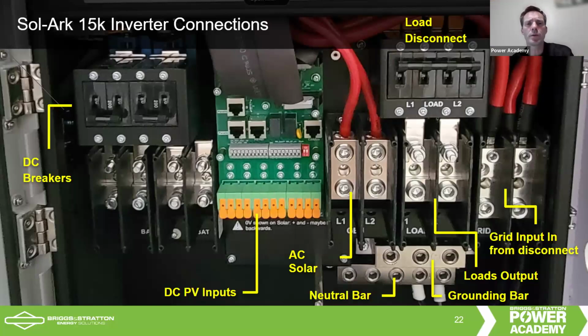So open circuit voltage on your panels should be a max of 550. Do take into consideration if you're in a place that gets quite cold, especially dry and cold, that you'll want to do temperature compensation if you're near that limit. And then the maximum operating voltage, the voltage of panels when they're actually outputting power, drops somewhat significantly, about 10 to 15% to hit the max power point, and that should not exceed 500. Those numbers you can get off the labels on your panels. Make sure to not exceed those values when you're creating your strings.